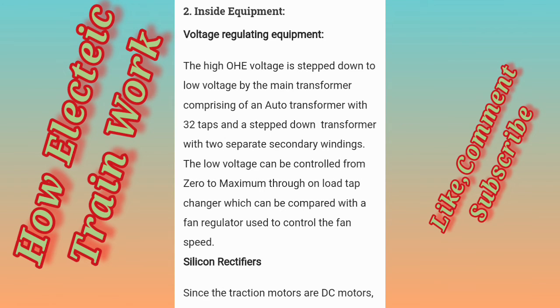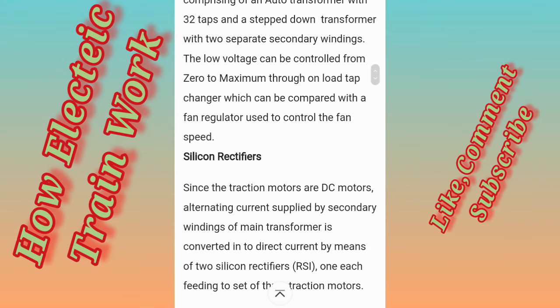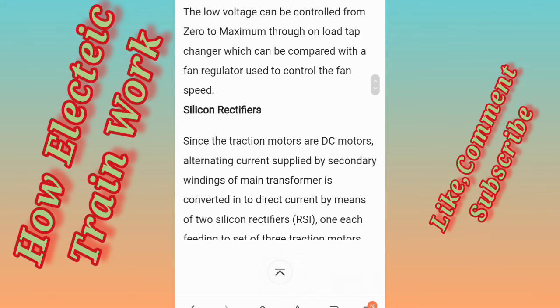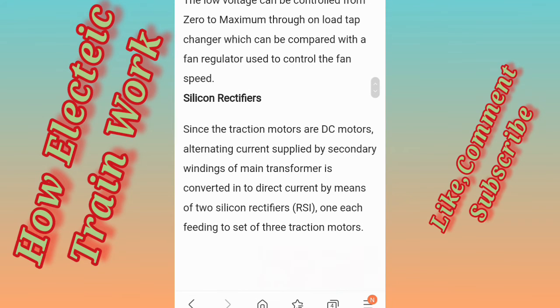Inside equipment, voltage regulating equipment. The high OHE voltage is stepped down to low voltage by the main transformer comprising an auto transformer with 32 taps and a step down transformer with two separate secondary windings. The low voltage can be controlled from 0 to maximum through the tap changer, which can be compared with a fan regulator used to control the fan speed. Silicon rectifiers. Since the traction motors are DC motors, alternating current supplied by the secondary windings of the main transformer is converted into direct current by means of two silicon rectifiers. RSI, one each feeding a set of three traction motors.